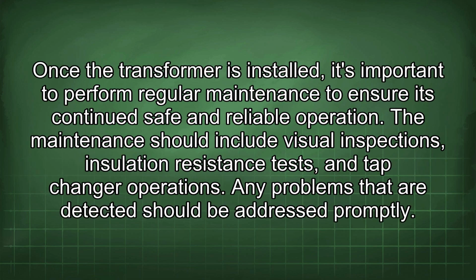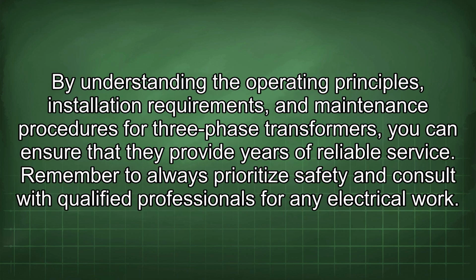Once the transformer is installed, it's important to perform regular maintenance to ensure its continued safe and reliable operation. The maintenance should include visual inspections, insulation resistance tests, and tap changer operations. Any problems that are detected should be addressed promptly. By understanding the operating principles, installation requirements, and maintenance procedures for three-phase transformers, you can ensure that they provide years of reliable service. Remember to always prioritize safety and consult with qualified professionals for any electrical work.